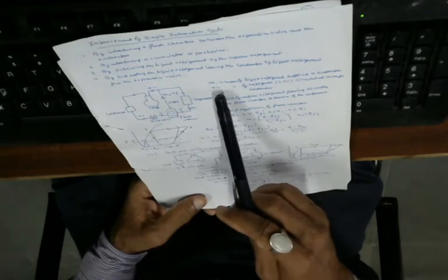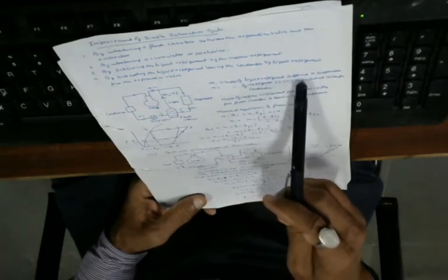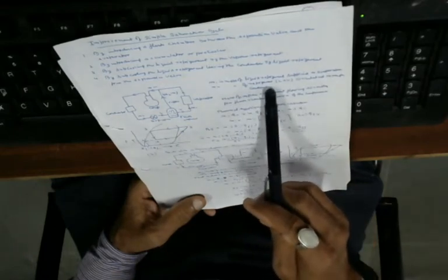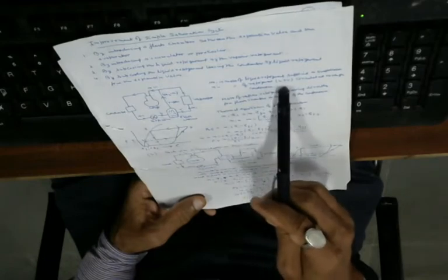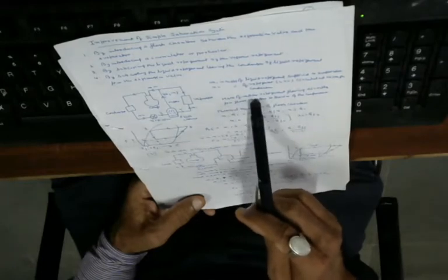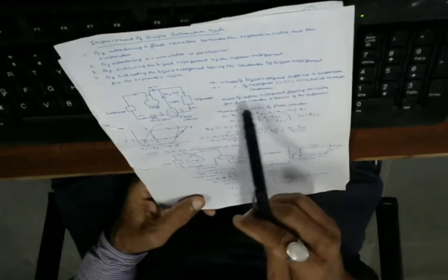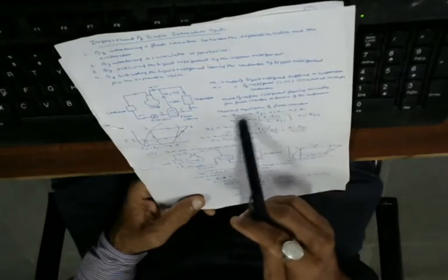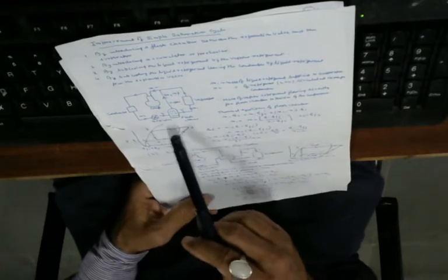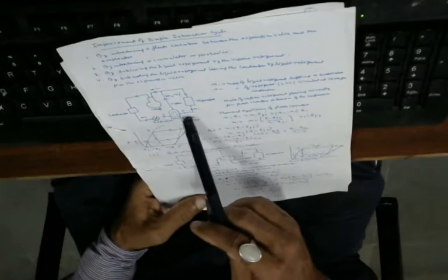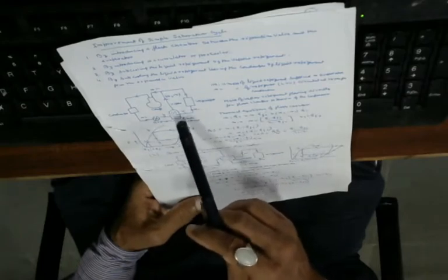Now M1 is the mass of the liquid refrigerant supplied to the evaporator. M2 is the mass of the refrigerant that is in the form of liquid and vapor circulated through the condenser. Then M2 minus M1 is the mass of the vapor refrigerant flowing directly from the flash chamber to the suction of the compressor. Therefore, thermal equilibrium of the flash chamber: what are the entrance point and what are the outlet points? Both are being balanced over here.